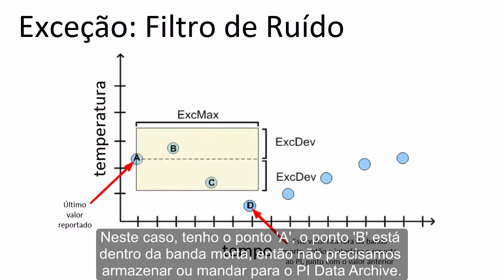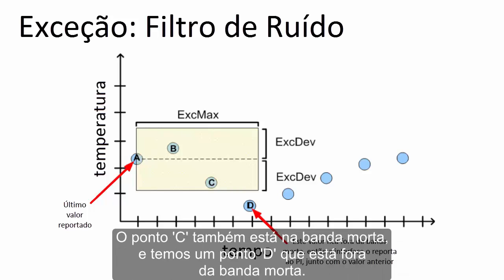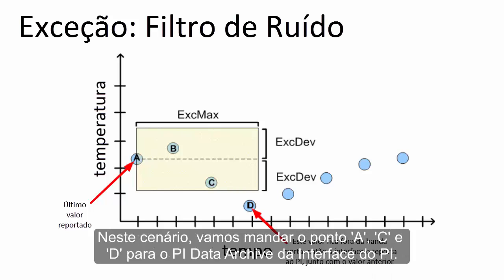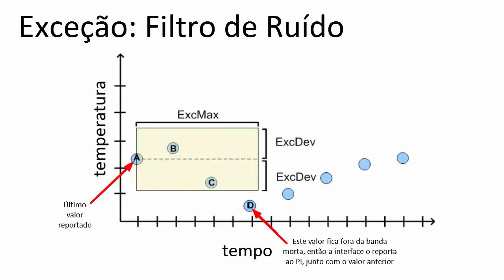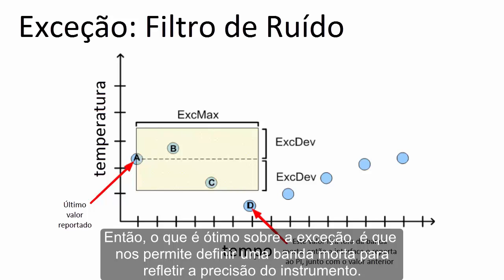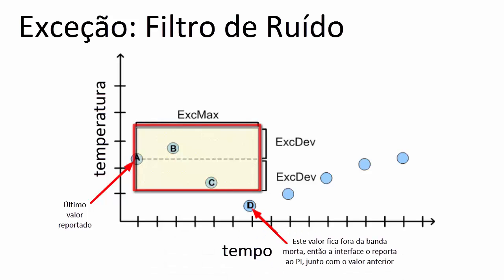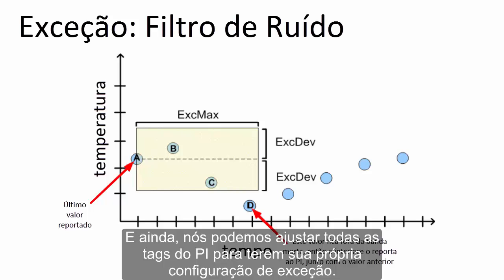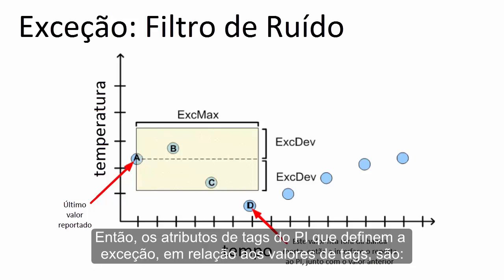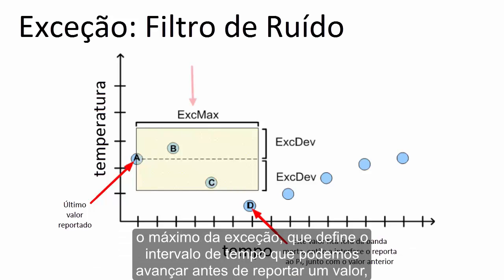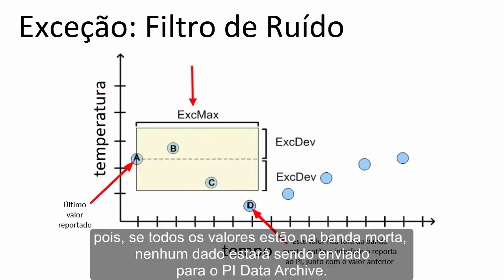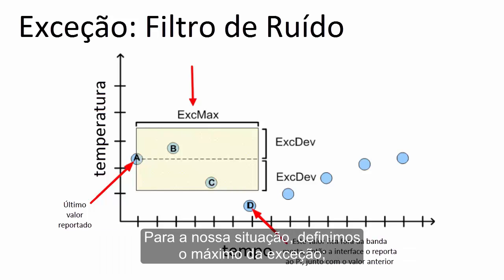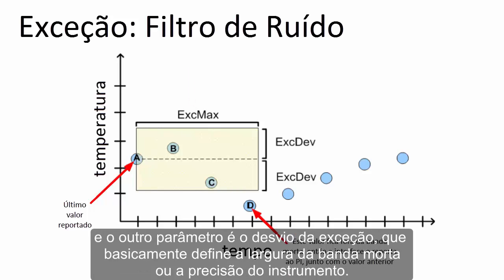Point A is coming in, point B is within the dead band so we don't need to store it or send it to the PI Data Archive. Point C is also within the dead band, and point D goes outside the dead band. In this scenario, we are going to send points A, C, and D to the PI Data Archive from the PI Interface. Exception testing allows us to define a dead band to reflect instrument precision, and we can individually tune all PI Tags to have their own exception setting. The PI Tag attributes that define exception are: exception maximum, which defines the length of time we can go before we must report a value — because if all values are within the dead band, no data is sent — and exception deviation, which defines the dead band width or instrument precision.